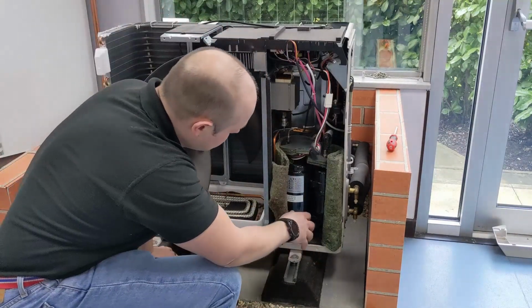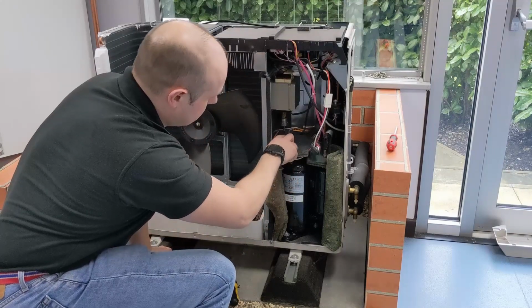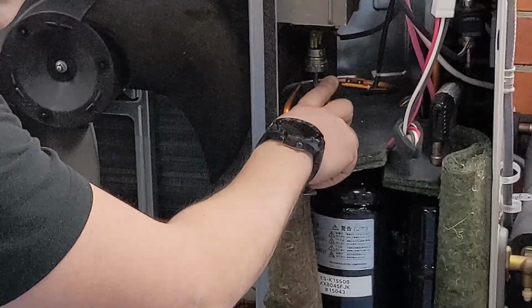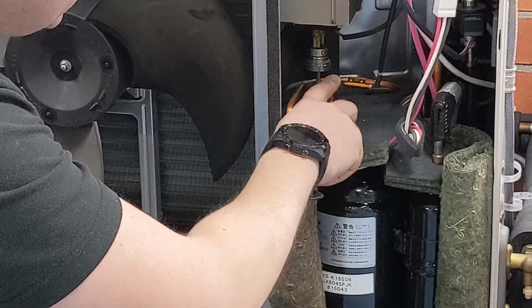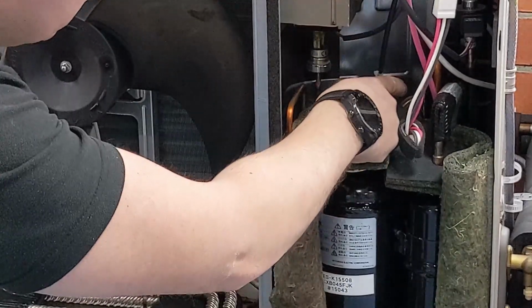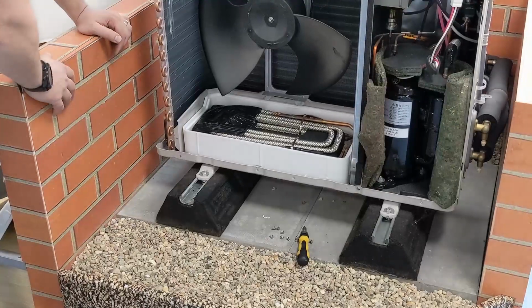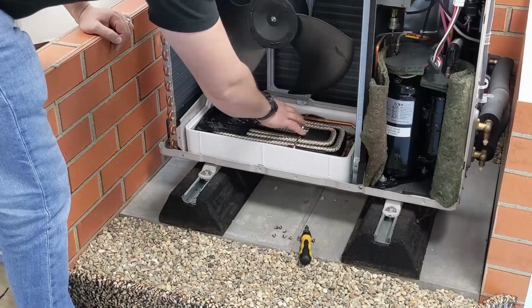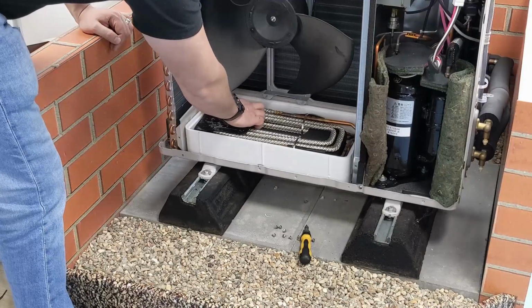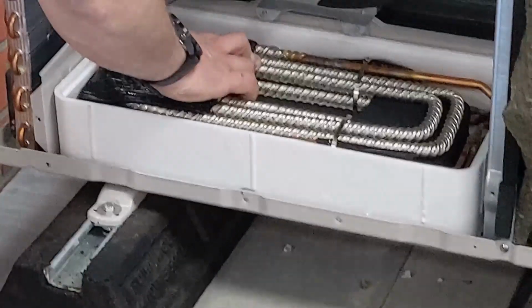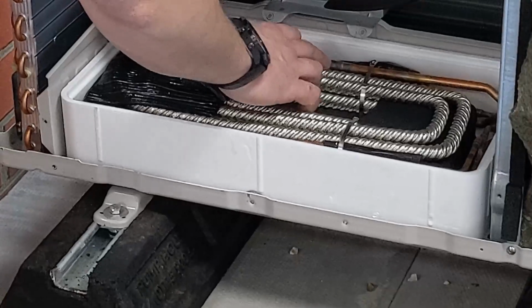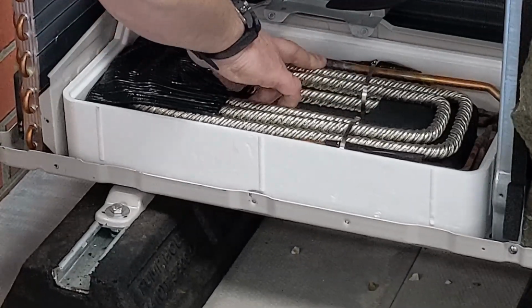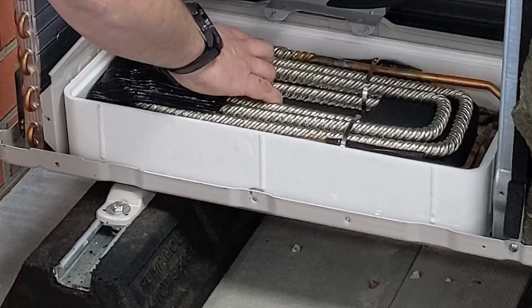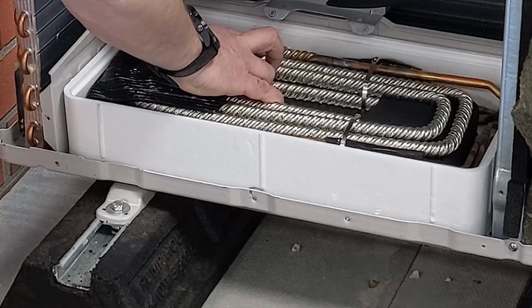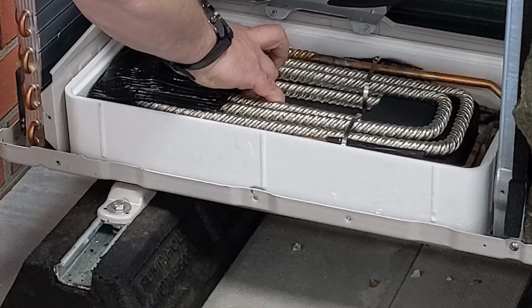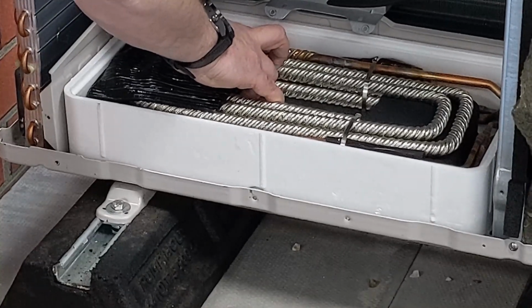So we've got refrigerant coming off the top of the compressor. From there, refrigerant's passing off to my heat exchanger. As the refrigerant passes through there, it's going to transfer energy from the refrigerant to the water. If you have a look there, we've actually got the pipe work going in there. That's the water pipe work, and then the refrigerant pipe work is wrapped around the outside of that pipe work and soldered into place to give good thermal transfer and making a very robust heat exchanger.